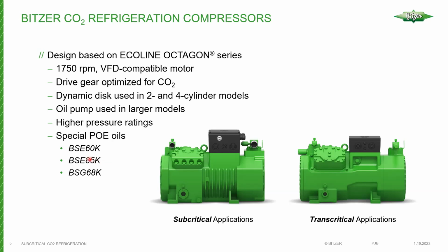Then there's the BSE 85, which is not used in subcritical compressors, but used in transcritical compressors. So in, for example, supermarket type booster systems, BSE 85K would be your standard oil. And then getting into the higher temperature applications, for example, heat pumps and what have you, once we cross a certain threshold in terms of pressures and temperatures, these would require the use of the BSG 68.